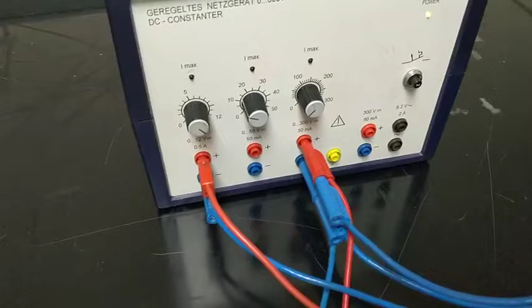10, 20, 30 until we reach 110. But before doing this, although the voltage is 0, there is some reading here, and we need to compensate for this reading, which means we need to do some calibration, and this device allows us to do calibration by using this small knob. I can change this to make sure that for 0 voltage we will have 0 electric field. So I'm just varying this, and I'm getting 0 volts equals 0 electric field. So this is just for calibration. Okay, so now this is calibrated, 0 equals 0, and I will start changing it.